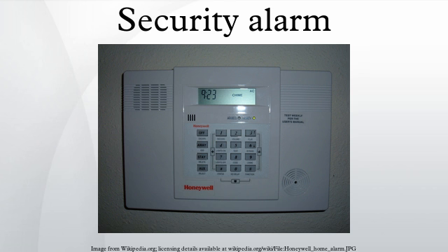The systems have adjustable electronics to permit installers to change the sensitivity of the alarm detectors to suit specific environmental conditions. The tuning of the system is usually accomplished during commissioning of the detection devices. Advantage: very cheap, very simple configuration, easy to install. Disadvantage: some systems have a high rate of false alarms because some of these sensors might be too sensitive. Although systems using DSP will largely eliminate false alarms in some cases.